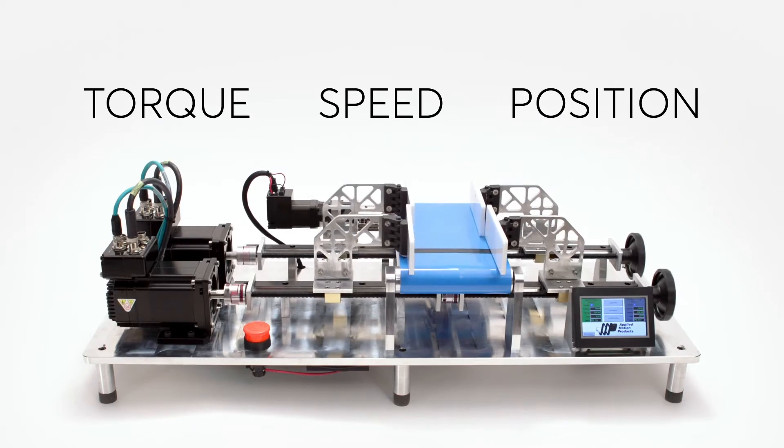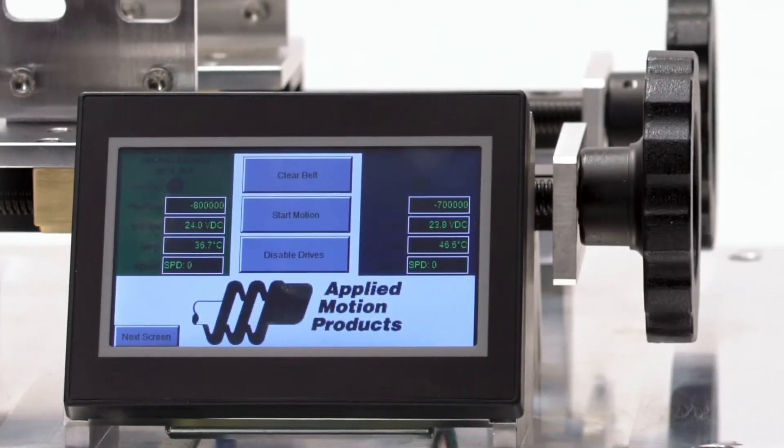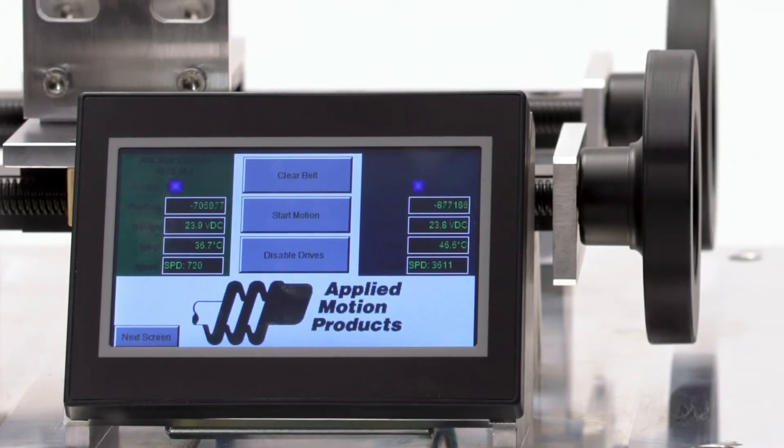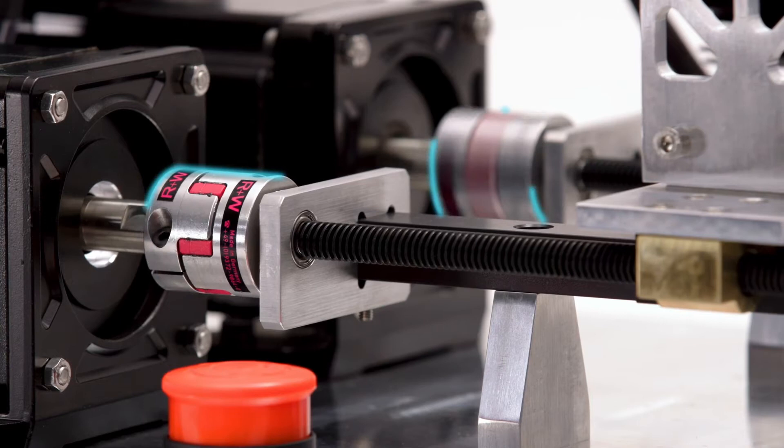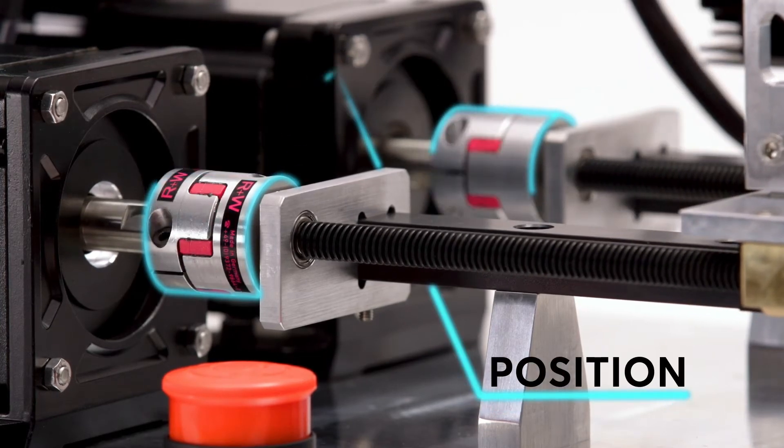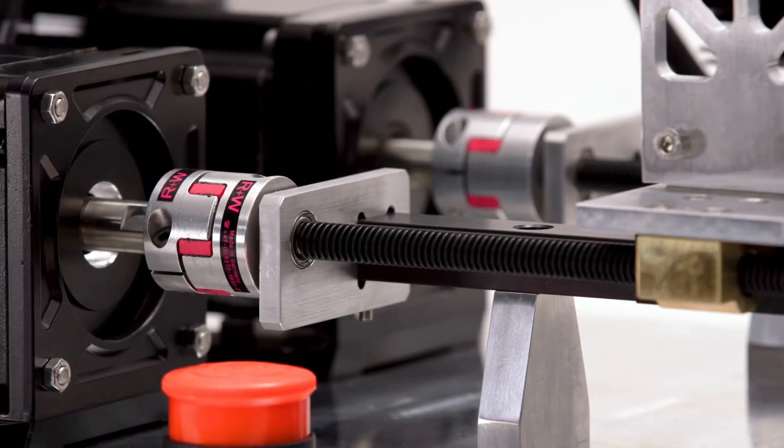In multi-axis machinery, the accurate position of every motor must be known at all times for the machine to operate successfully. A critical step in the operation of a machine is to determine the position of every motor in relation to the others. This is done by homing each motor to a known physical location and is usually done at power-up or during initialization.